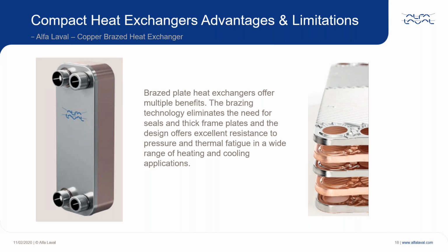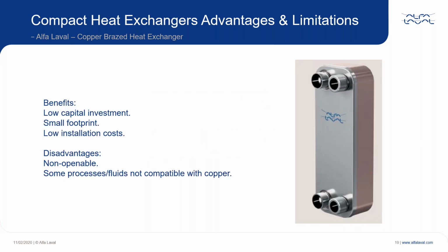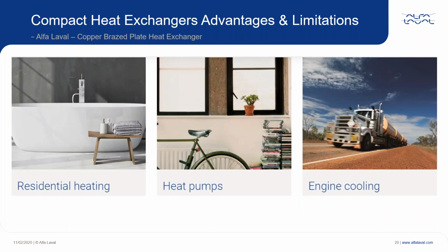The smallest one of our ranges are copper brazed units. These are mainly used in heating and ventilation units. They're made by sandwiching copper sheets between the stainless steel channel plates. They're clamped together and put in an oven, and it brazes the plates together. This method eliminates the need for seals and thick frame plates, so they're quite compact units. So the benefits of these are low capital investment, a small footprint, and low installation costs. Unfortunately, copper is not really great with a lot of fluids, so often that makes these non-suitable. And as I mentioned, residential heating, heat pumps and engine cooling are their main areas of use.